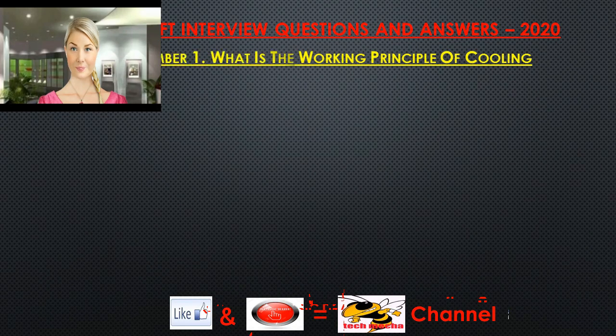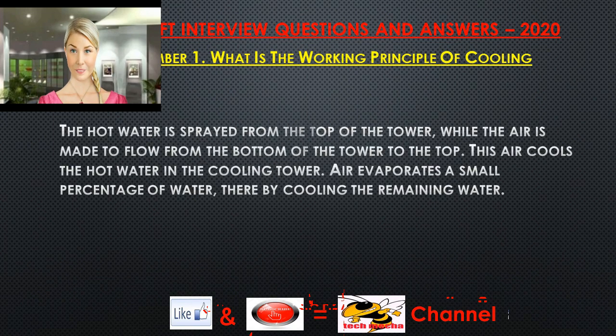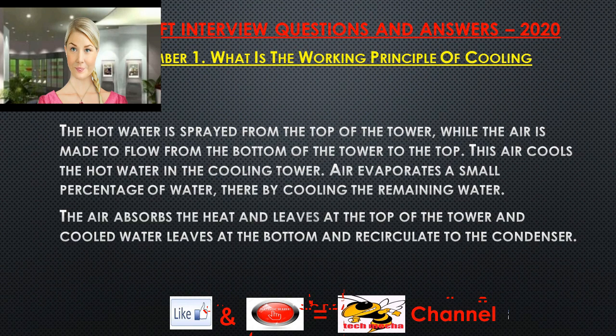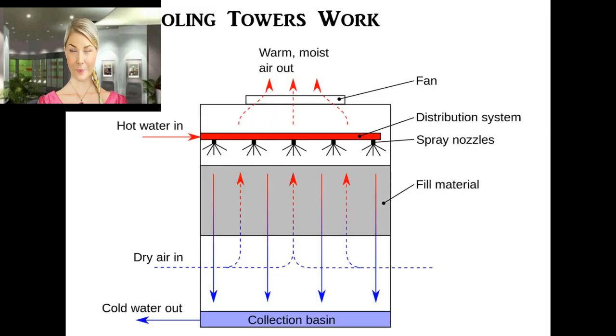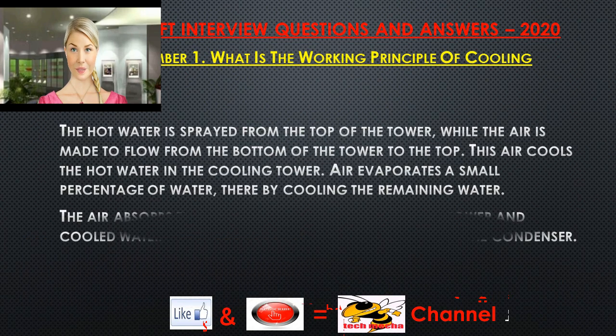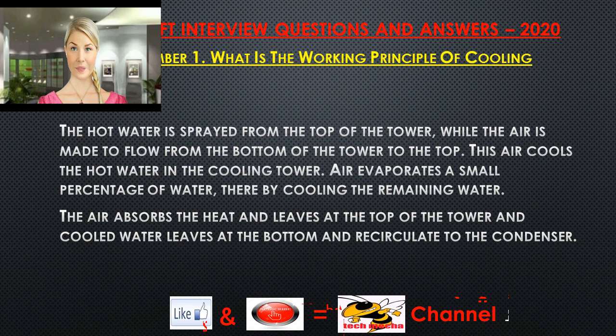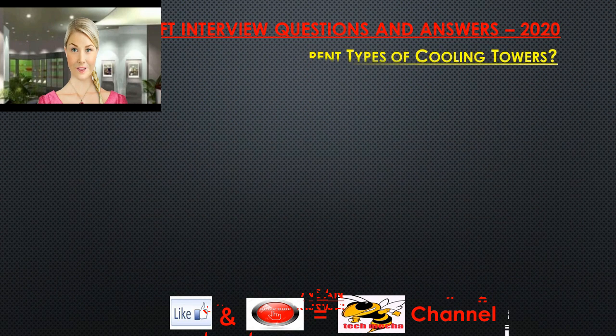Question 1: What is the working principle of cooling towers? The hot water is sprayed from the top of the tower while air is made to flow from the bottom to the top. This air cools the hot water; it evaporates a small percentage of water, cooling the remaining water. The air absorbs the heat and leaves at the top, and cooled water leaves at the bottom to recirculate to the condenser.